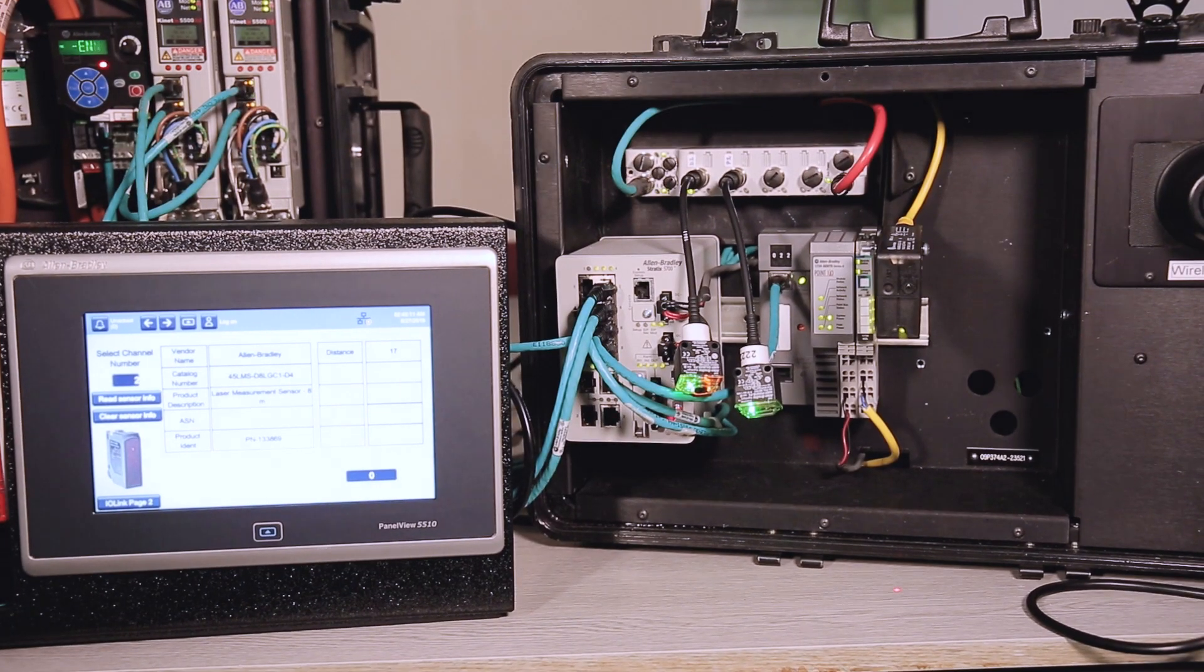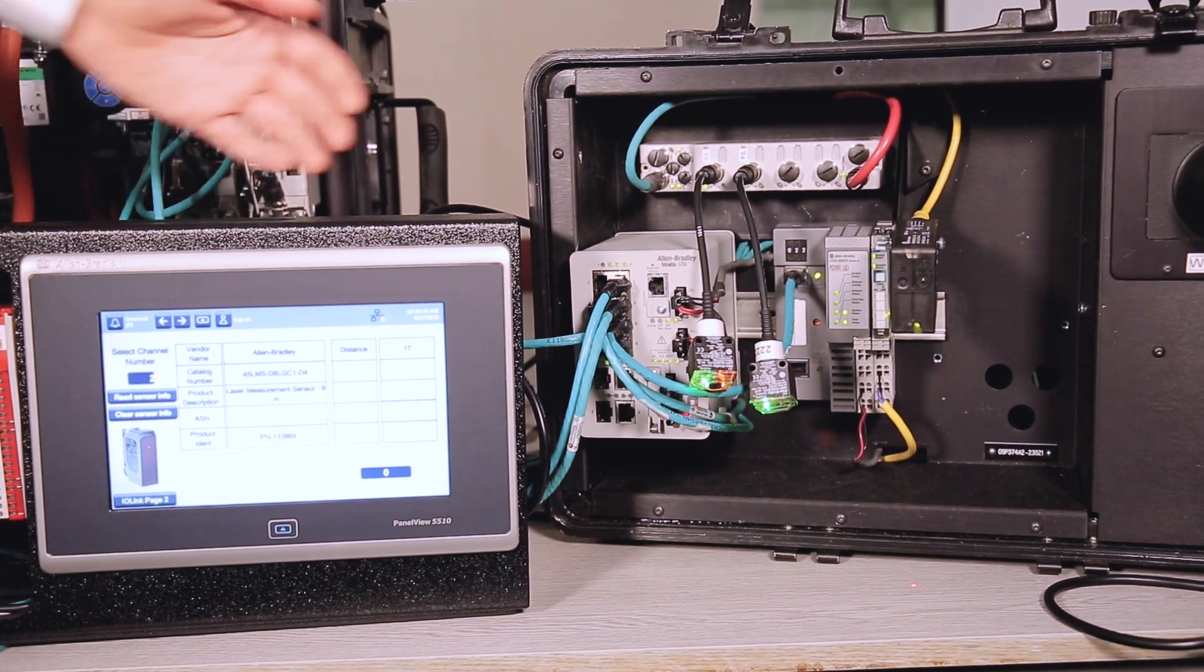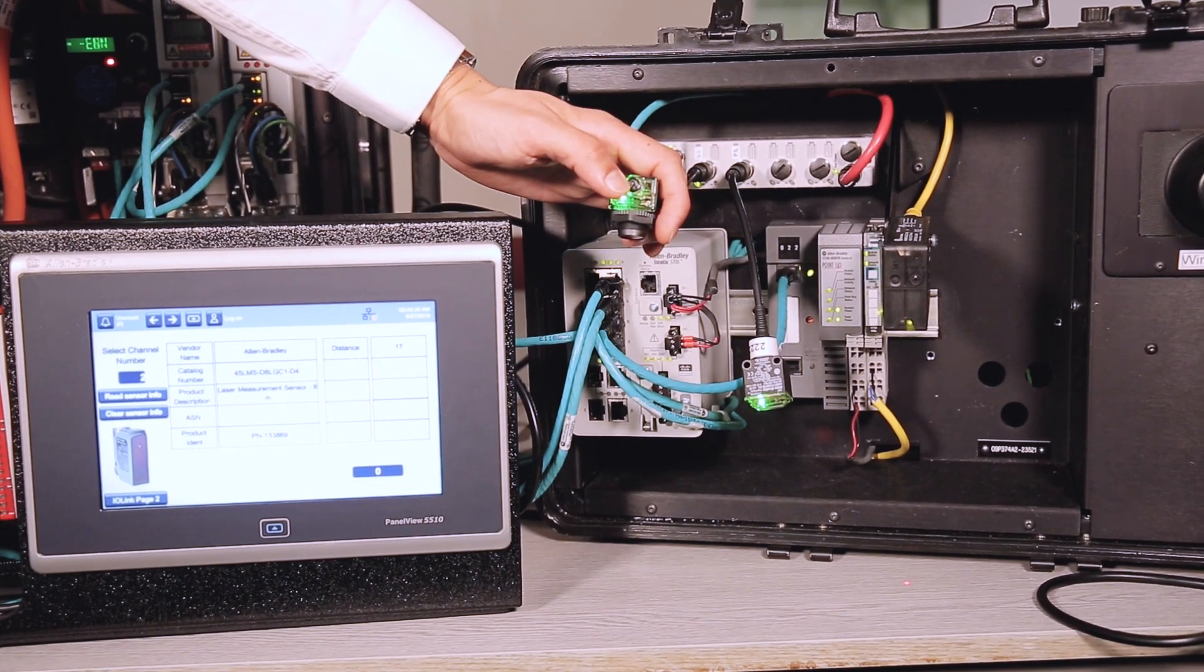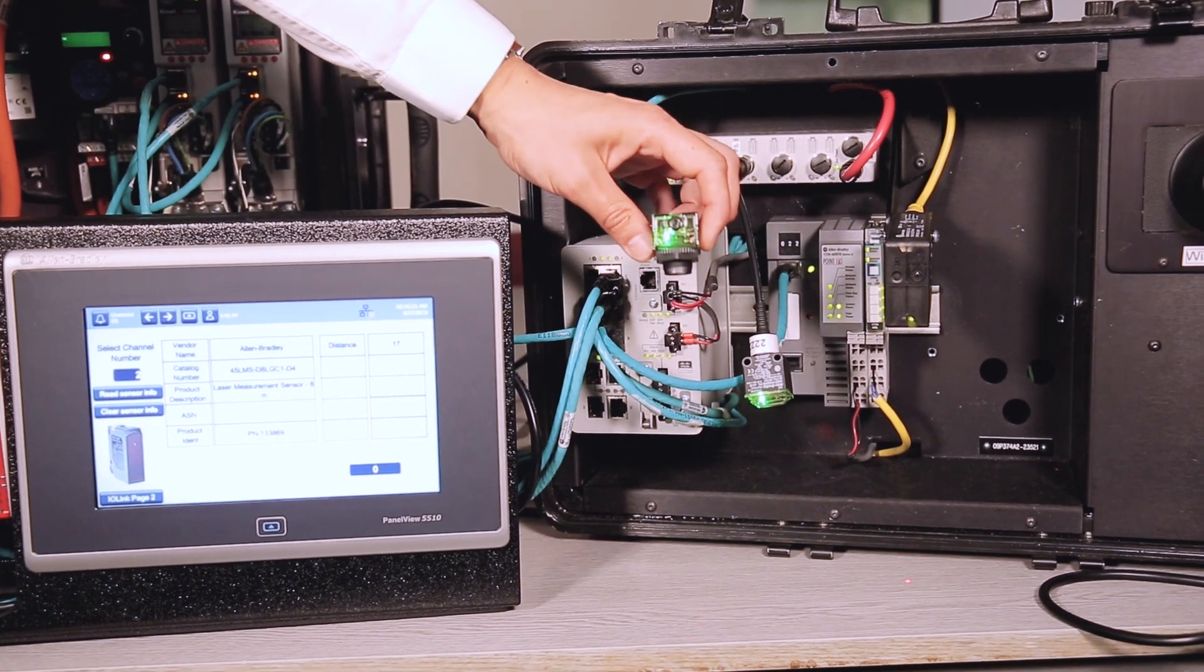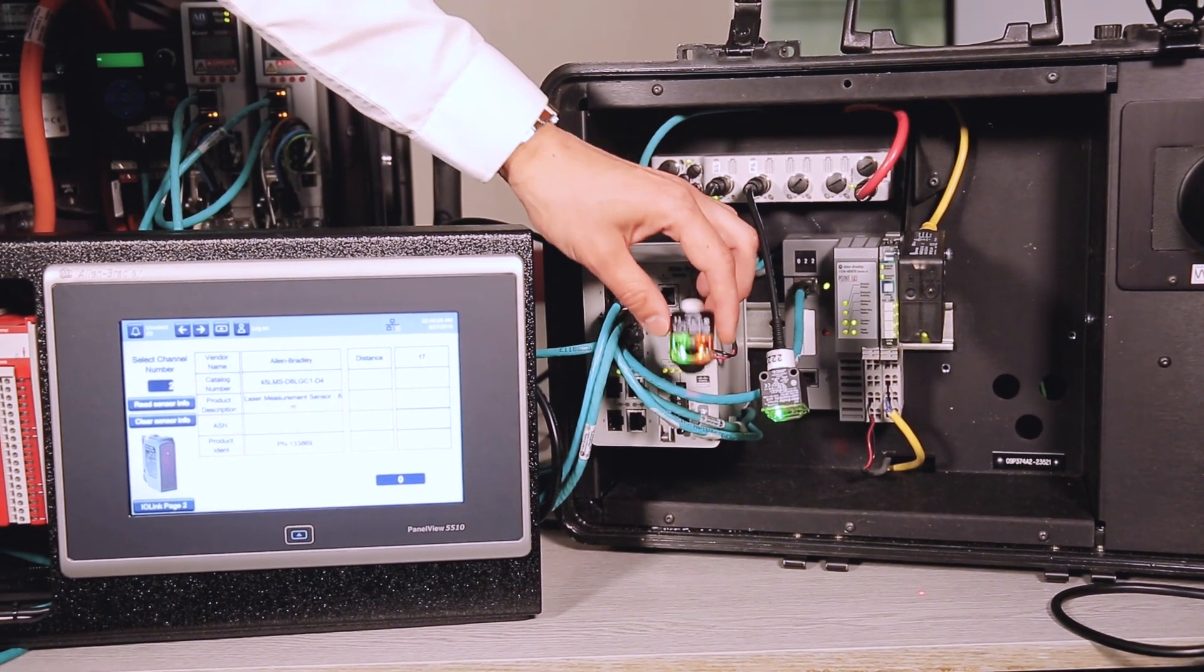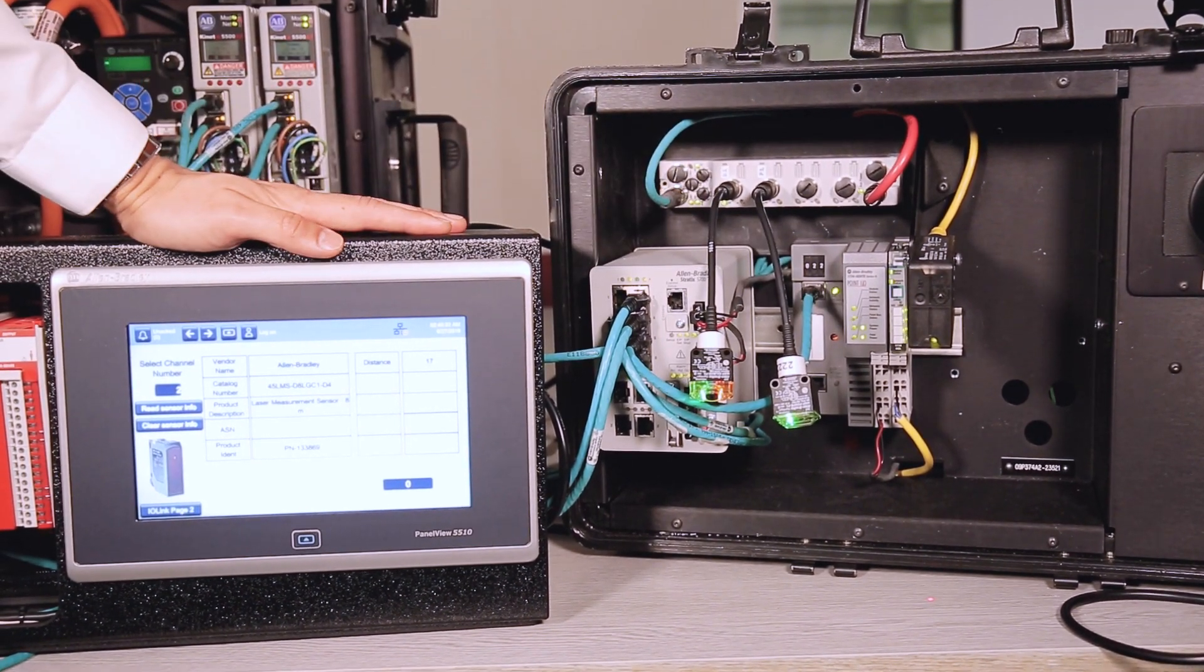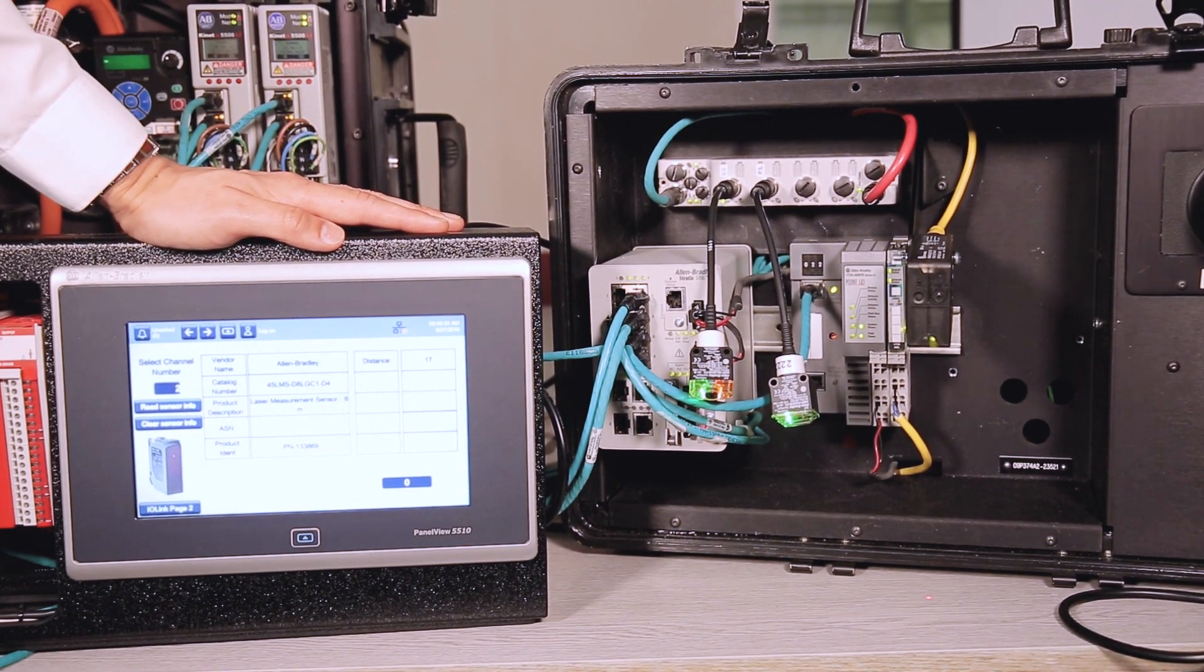Traditionally, sensors are a fairly simple product which are taught locally by the operator or the installer using a local adjuster or a teach button on the device. Obviously this can lead to issues with changeover times with product variants. So by using an IO-Link enabled sensor, you can get the full details and diagnostics out of a sensor, as well as sending remote teach and reteach functions.